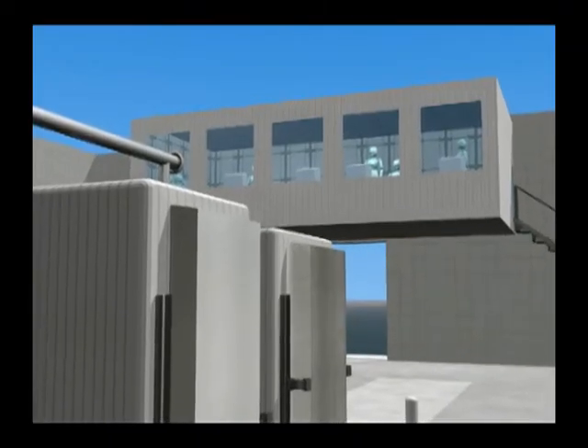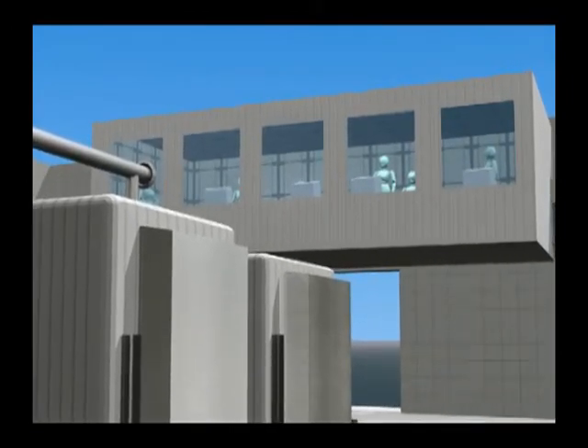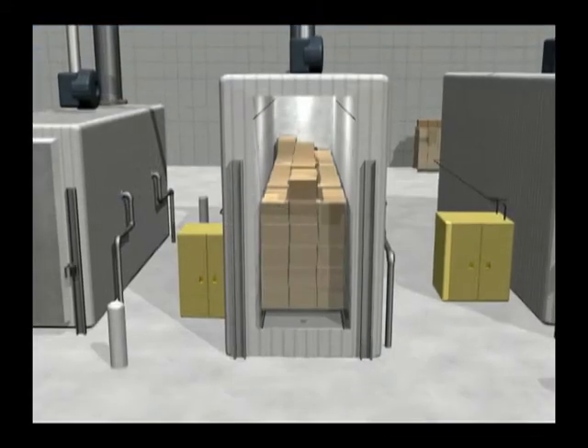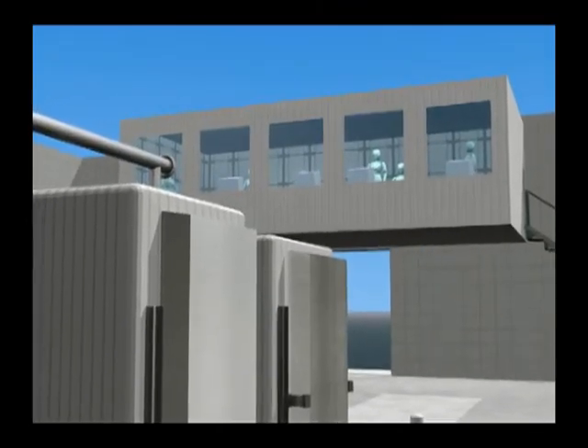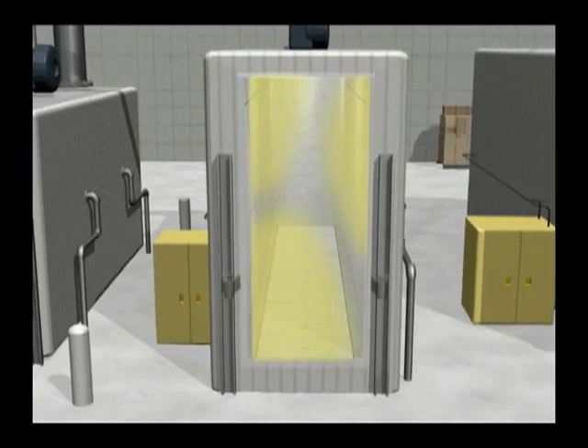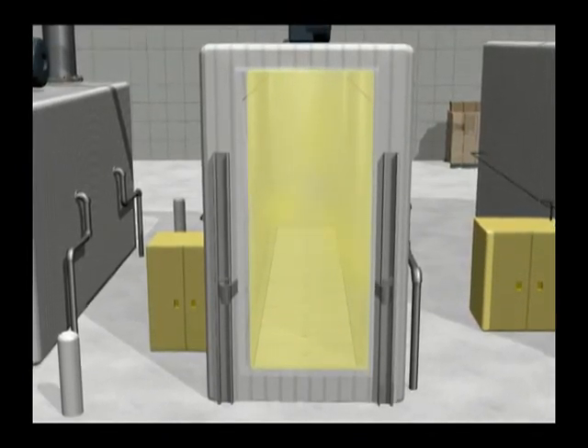Operators in the control room instructed the computer to abort the sterilization cycle and remove the gas. The system automatically performed the normal series of gas washes, which removed virtually all of the ethylene oxide. Finally, the chamber was ventilated to the oxidizer. Operators then removed the products from the chamber. Maintenance technicians arrived and performed tests, which did not reveal any problems. They then ran a test cycle that injected 120 pounds of ethylene oxide into the empty chamber, and again they could not identify a problem.